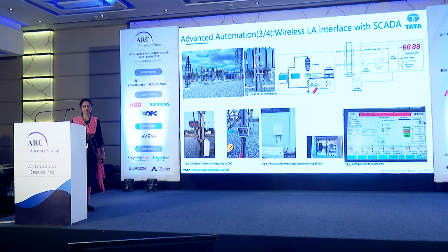Solar plants cover a very huge area, in terms of thousands to tens of thousands of hectares, so it's very difficult for a person to go to each transformer or lightning arrestor module to check the counter. In this case, we implemented a wireless lightning arrestor interface wherein the digital data is available on my SCADA screen. As soon as the lightning strikes, I get the information in my SCADA system, time stamped, and this data is useful even for insurance purposes.